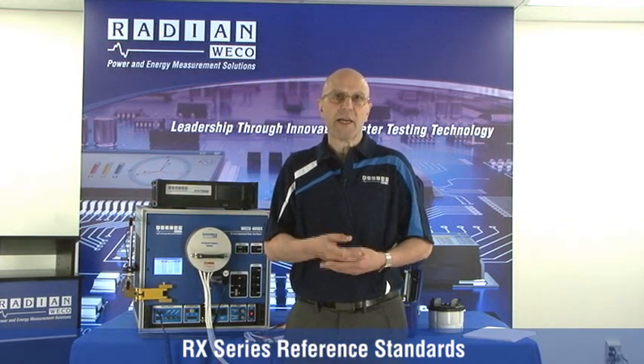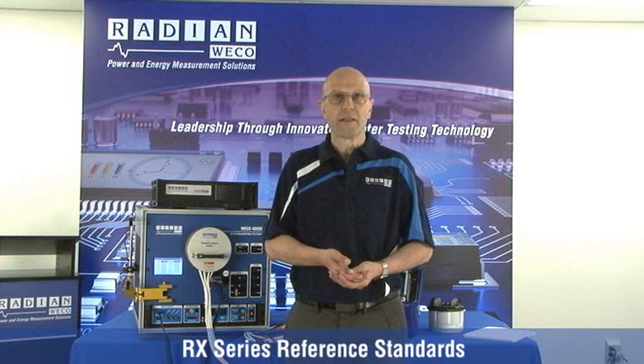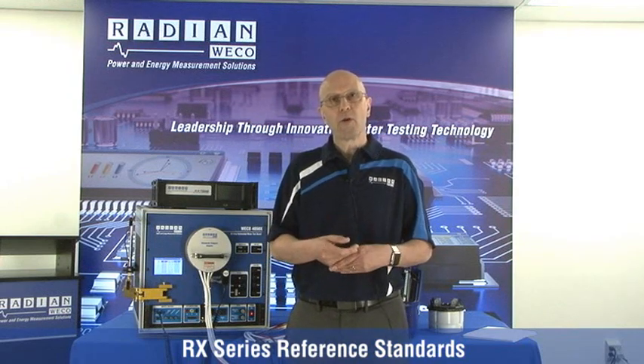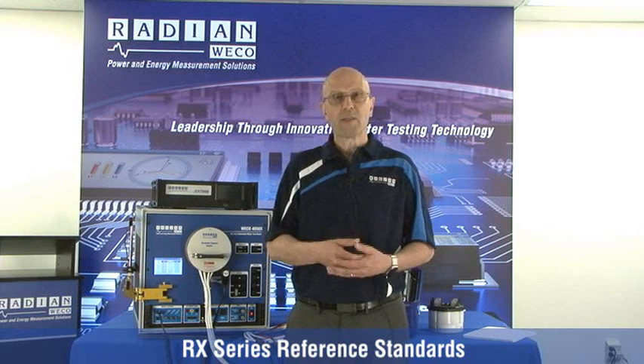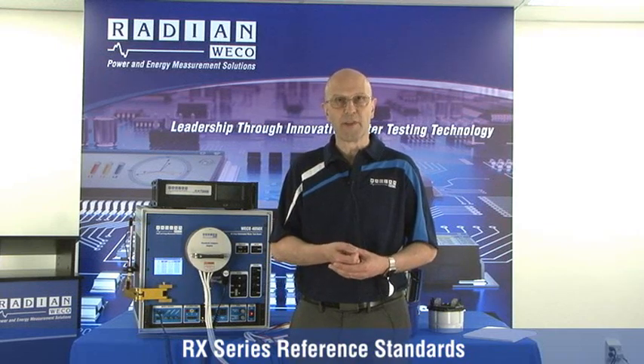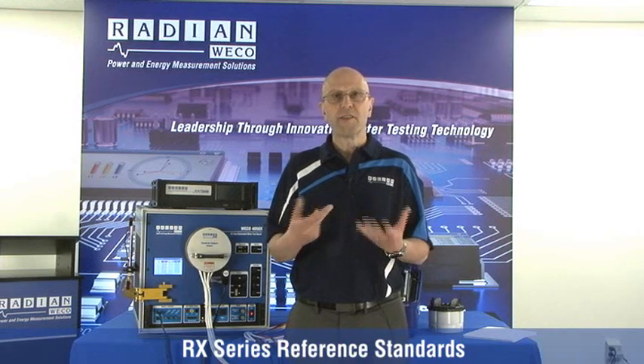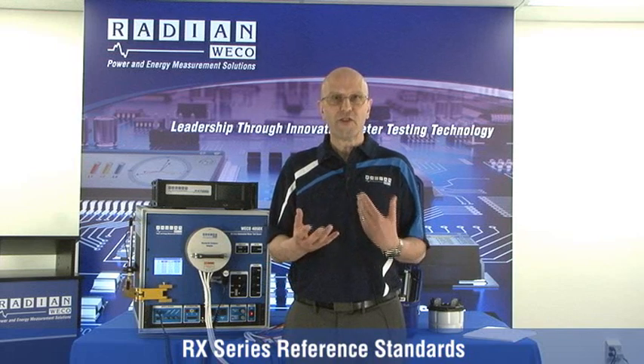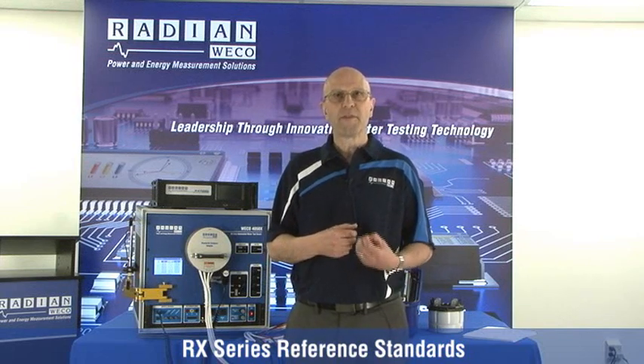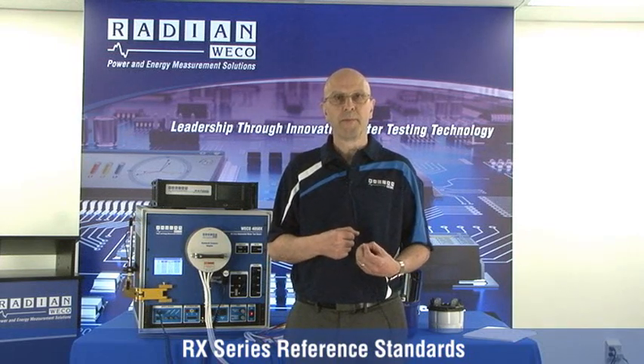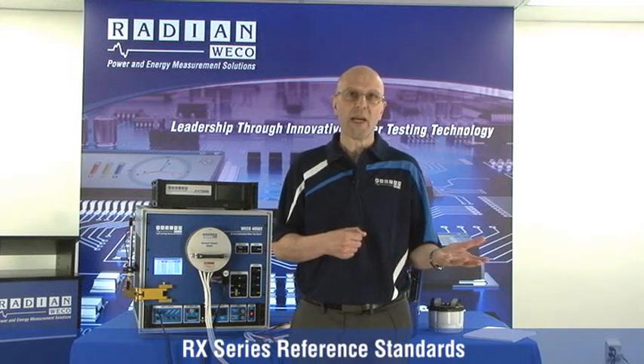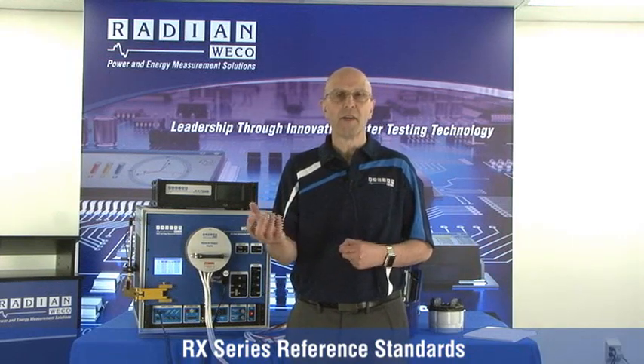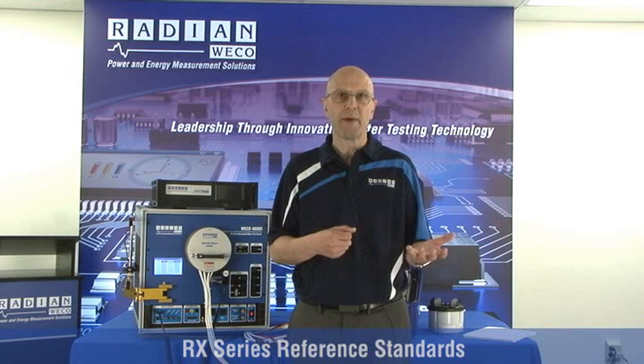The measurement algorithms for the RX series are different from the RD series. The RX series now incorporate time domain as well as frequency domain type measurements. This allows us to select the best digital algorithms for the types of measurements that you wish to perform. Whether you're handling pure sine waves or full harmonic content, you may wish to switch between time domain and frequency domain type measurements.